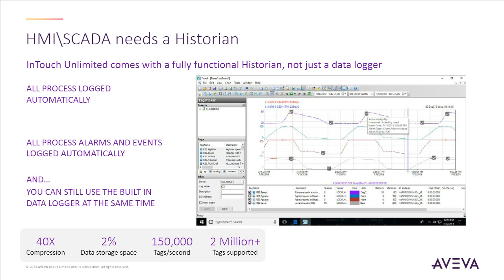One of the things an HMI SCADA system most likely needs in a lot of applications is a historian. InTouch Unlimited Premier comes with a fully functional historian—InTouch Unlimited Premier or above, including the Operations and Control Edge Edition that John talked about earlier. This simply allows you to log all process information automatically, all alarms and events logged automatically. And of course, InTouch still has the data logger built in, so you can still use that. You get all the advantages of a historian with 40 times compression, 2% of the data storage, 150,000 tags a second, up to 2 million plus tags being stored in the historian.